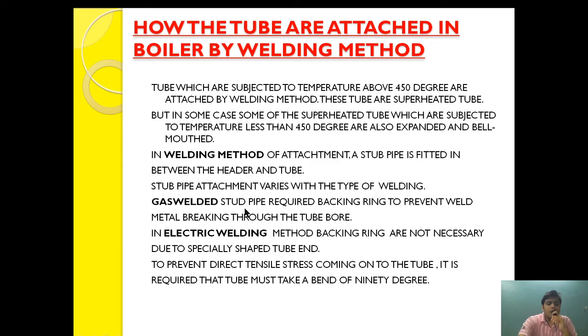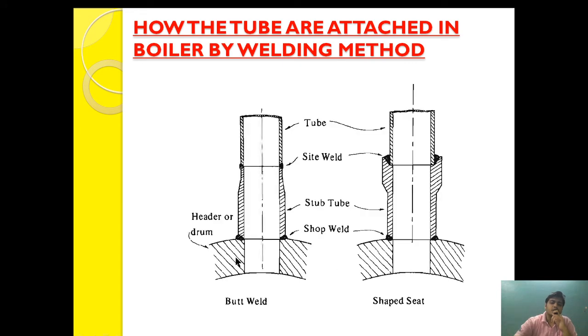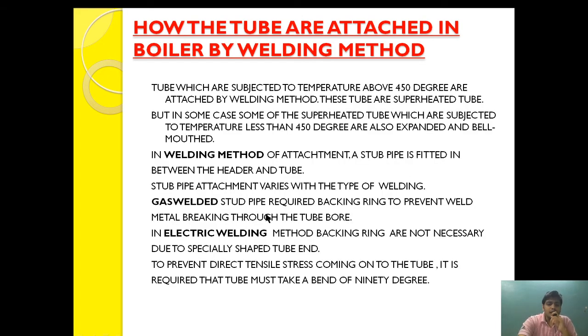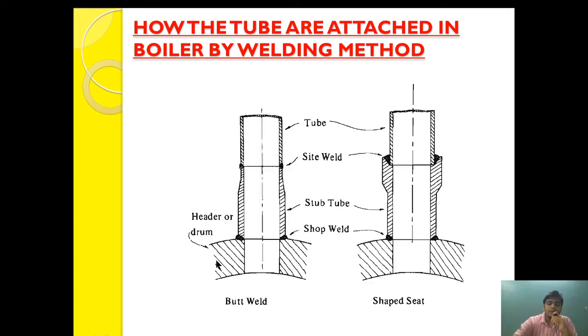Gas weld stub pipes require a backing ring to prevent weld material from breaking through the tube bore. In the case of electric welding, backing rings are not necessary due to the specially shaped tube end. As you can see in this diagram, the gas welding stub pipe has a backing ring, whereas the electric welding stub pipe does not require one.